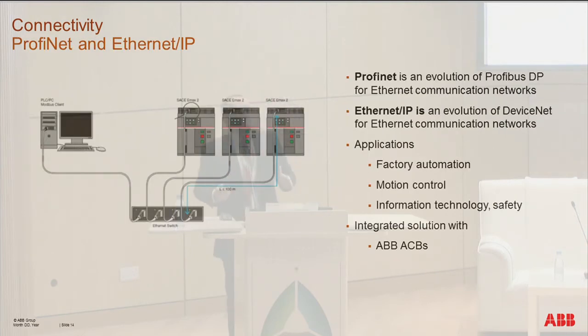The Profinet and the Ethernet IP. Profinet is an evolution of the Profibus DP that we mentioned, for Ethernet communication networks, and Ethernet IP is the evolution of DeviceNet for Ethernet communication networks. Both protocols are used for supervision and controlling the system, with applications like factory automation, communication between PLC and motor controllers and motor starters. These two protocols are also integrated in ABB EMAX2 without the need of any external converters.